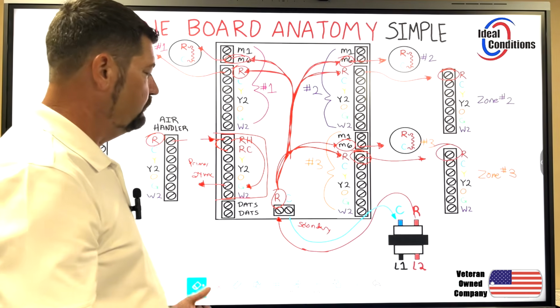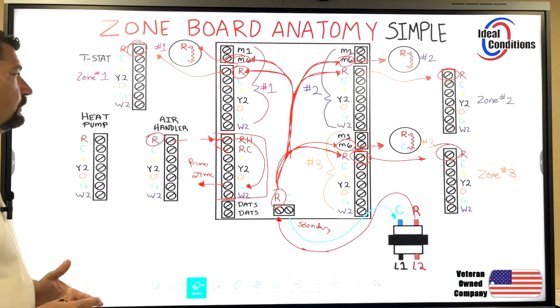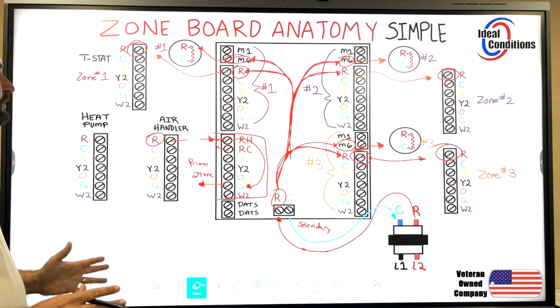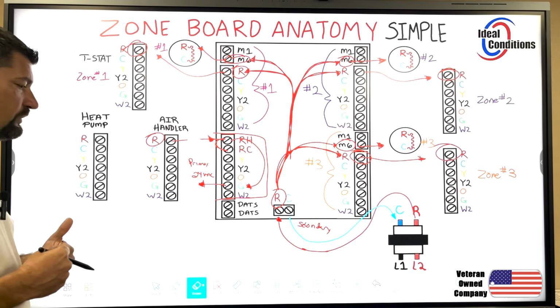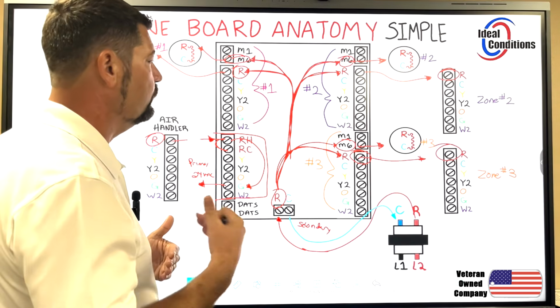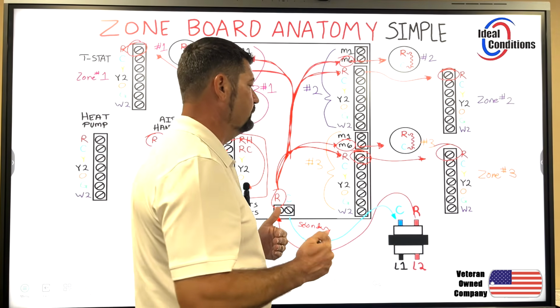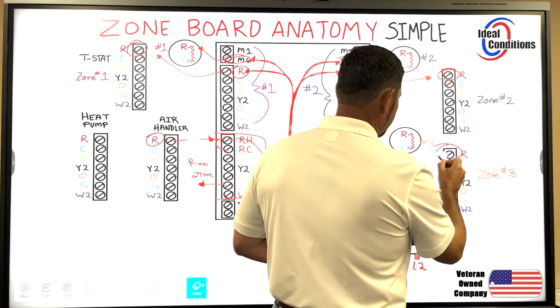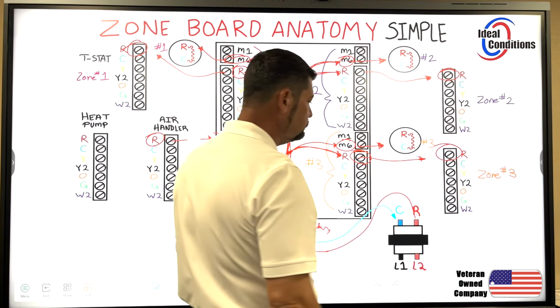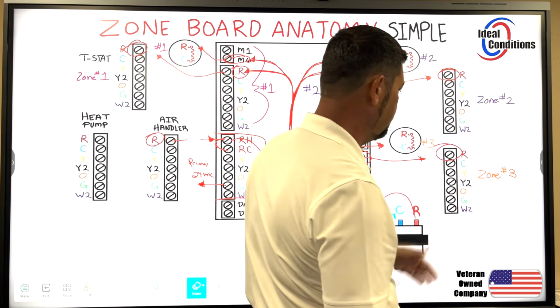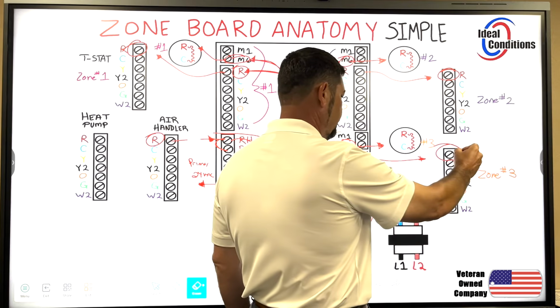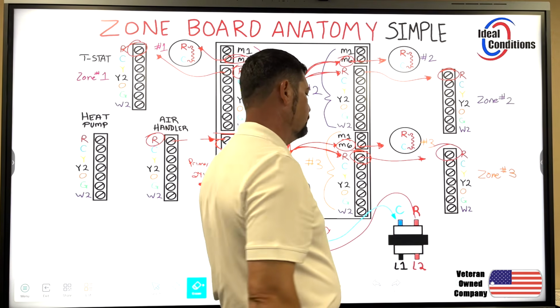And so people get confused with these secondary transformers, and I don't know why. It's a very simple thing, but you've got to be able to take an extension of your understanding of how the thermostat works. All a thermostat needs is 24 volts here, and the moment it calls, it's going to relay that power to all the corresponding terminals.